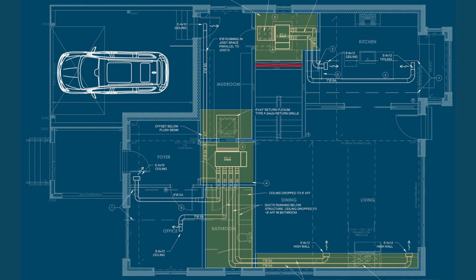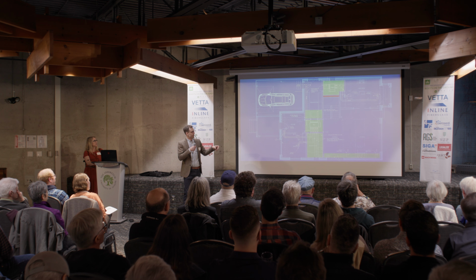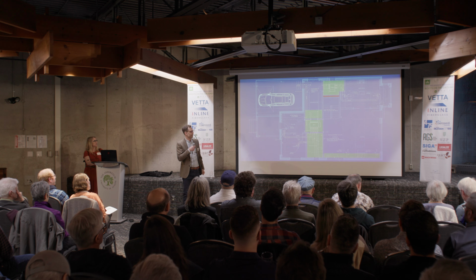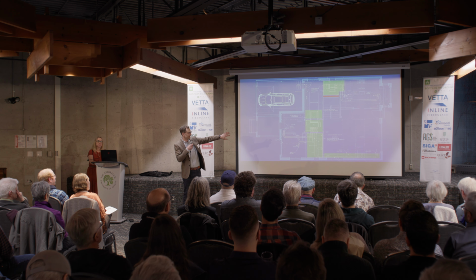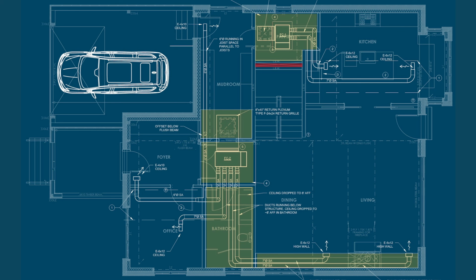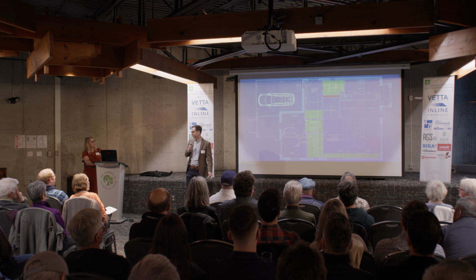Below that, you see a red bar. That's an 8.5-inch chase that goes from the mechanical room in the basement all the way up to the top of the house. And that way we can run ventilation ductwork and a central dehumidifier ductwork that circulates through the home. And the hydronic piping comes through there and then branches out to the fan coils. We have a second one here, again with a removable ceiling. We kept the ceiling low at 8 feet through the bathroom, and there is one bulkhead. Everything else has been coordinated and runs through the TJIs. So no impact to the ceiling.